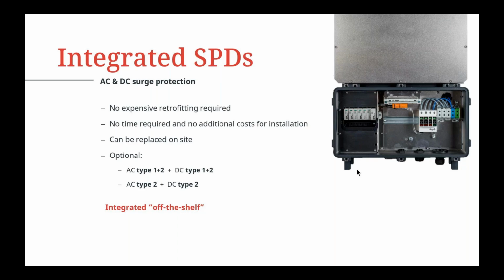So you have two options in this particular inverter design: you can opt for type 1 plus 2 AC and DC SPDs, or type 2 SPDs only, at the time of ordering the inverter. Whenever you order the inverter, you just have to select either type 1 plus 2 or type 2 only, and they will come integrated at the same cost. So it will not only save the cost for the whole system, but also the time and the costly installations and external DBs at the time of installation. It is not only flexible in terms of PV system design, but also really handy at the time of installation, with fewer complications.